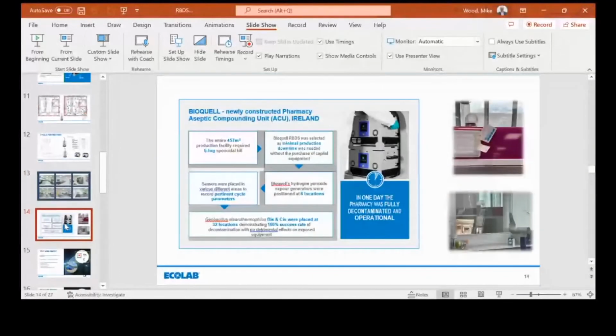So, a newly constructed pharmacy aseptic compounding unit, ACU Ireland. The entire target area is 457 meters cubed. Bioquell RBDS was selected as minimal production downtime was needed without purchasing capital equipment. Sensors were placed in various areas to record the full parameters of the cycle, including parts per million and relative humidity. BioQuell hydrogen peroxide vapor generators were positioned at 6 locations, as shown on slide 7.